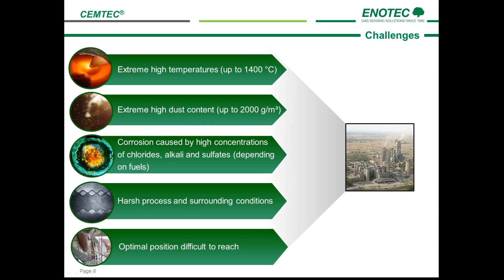The challenges in this application are clear: high temperatures above 1,000 degrees, dust concentration of up to 2,000 grams per cubic meter, high concentrations of chlorides, alkaline, and sulfates depending on the fuel used. This can lead to corrosion of the equipment and harsh ambient conditions. Last but not least, an optimal probe position for reliable process values from the kiln is required. Now let me explain how we at ENOTEC have continuously developed our CEMTEC system in order to overcome all of these challenges.